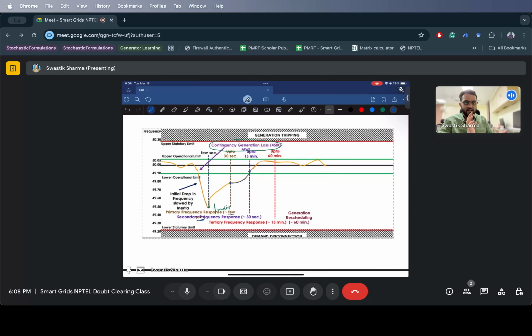So you see there is a significant delay between the time at which the secondary frequency response kicks in and the time it was issued. And if it is still not within the certain band, if I continue this at this point, the system may not be back to 50 hertz. So what I do now is initiate a tertiary frequency response, in which I buy frequency support from the ancillary service markets. This continues for another 60 minutes, and now my frequency is back in the stable operating range. So this is what happens.